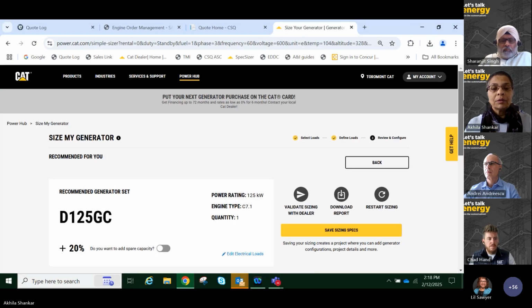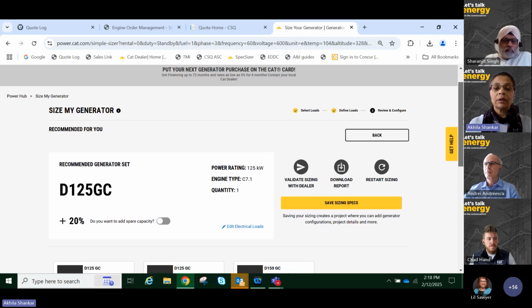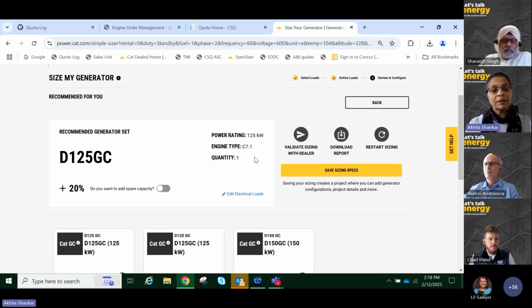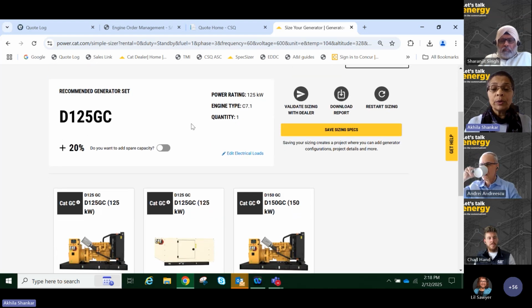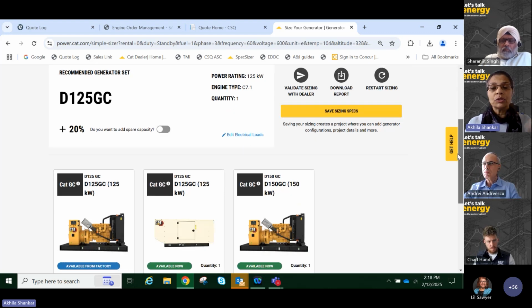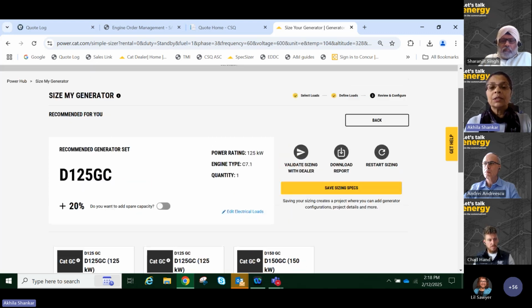I have to give the program a few seconds to come up with the recommended generator set for the given set of loads. PowerHub recommends a 125 kilowatt diesel generator. The model is C7.1, also referred to as the D125GC. You have the option of adding an additional 20% capacity to the loads that you've already entered for future expansion if required. You can also go back and edit these loads even at this stage.